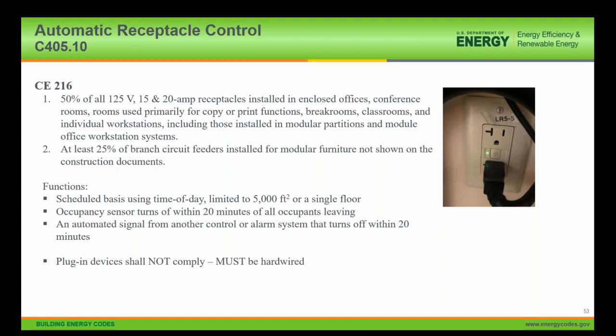A simple way is through a scheduling basis. However, there are some limitations in that you have to limit it to about 5,000 square feet per section that you are scheduling together, or a single floor. You can also do it through an occupancy sensor, where after 20 minutes of inactivity in a space, the controlled loads are turned off. And you can also do it through an automated signal from another control system, maybe a building alarm or some other means. Again, that 20 minutes kicks in either way. It's important that it be a permanently wired-in device, so plug-in devices cannot comply; it must be hardwired.